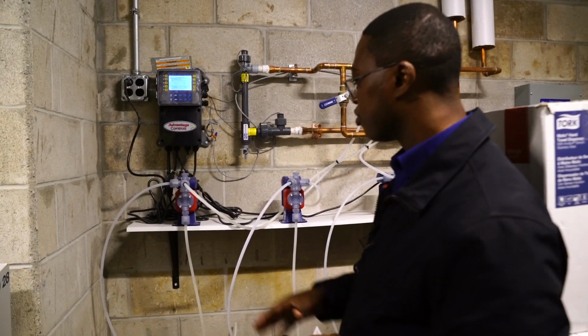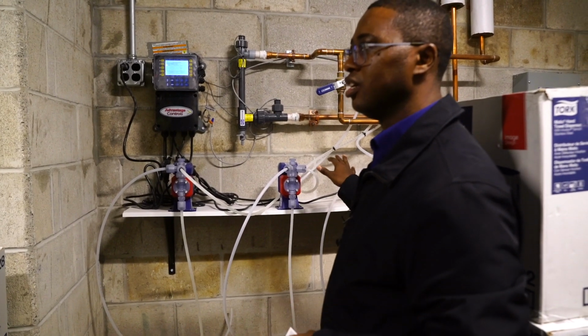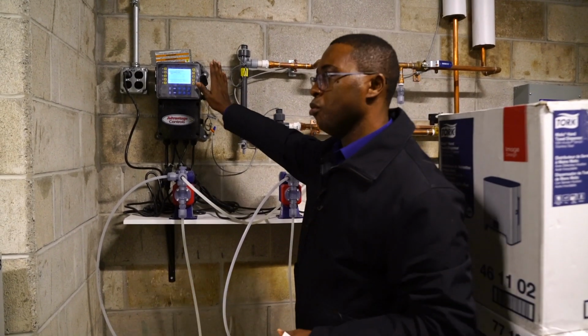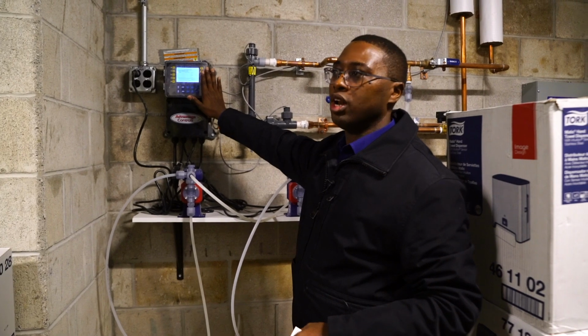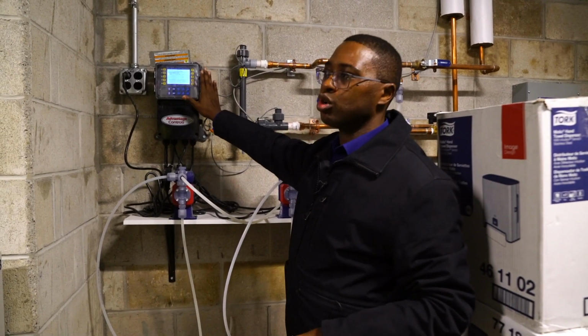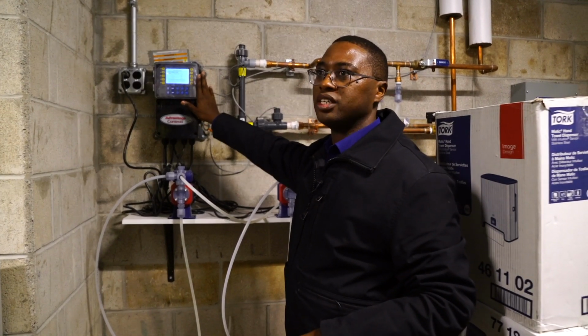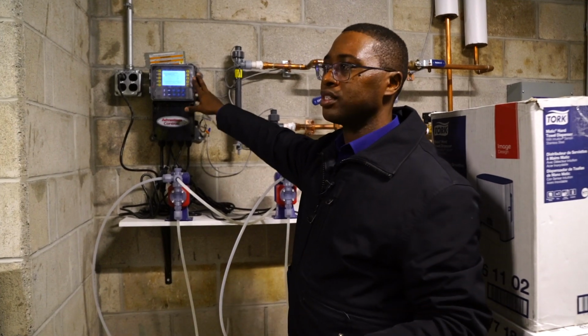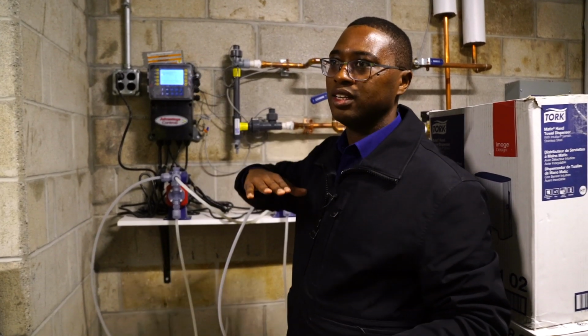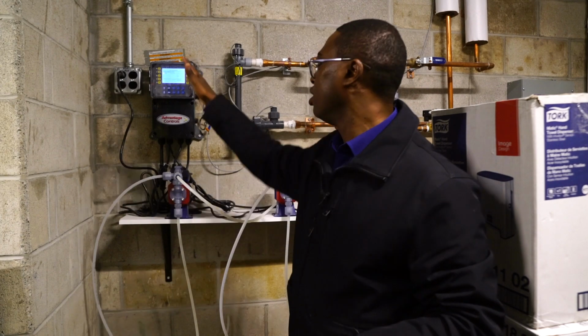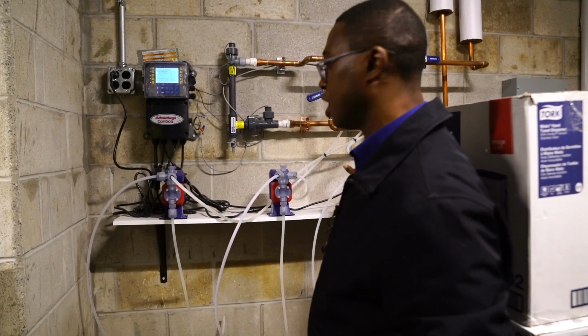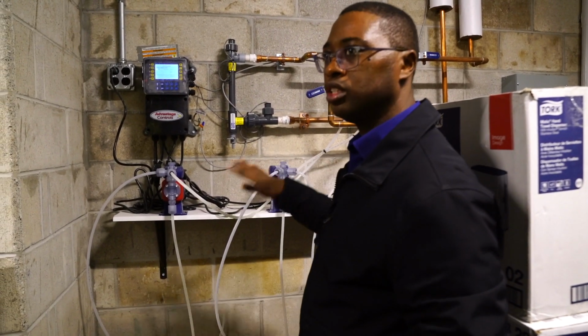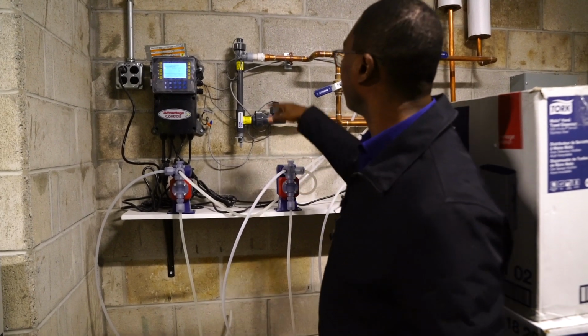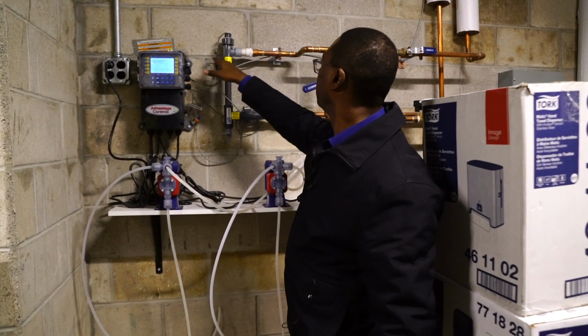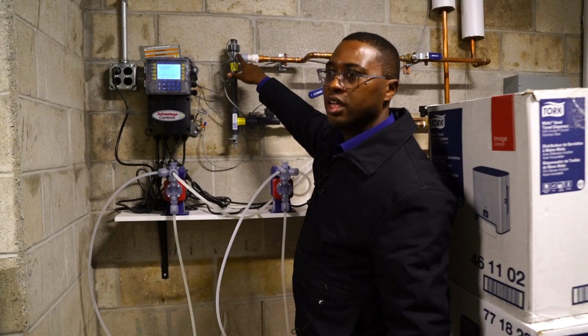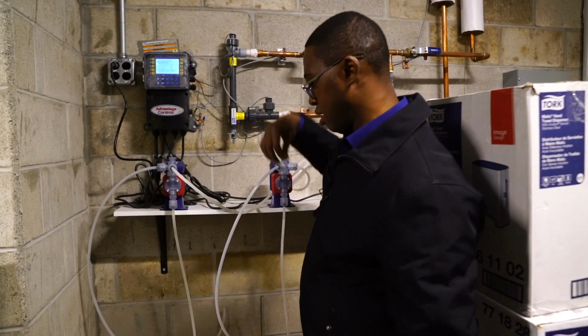No problem. So here you have 3 different types of chemicals for your cooling tower, and they're operated by this controller. This controller uses flow for operation. If your cooling tower pumps, for some reason, stop working or you shut them down, this should be able to cut off these chemicals, right? It should stop operation of this because there's a flow sensor here that operates your cooling tower.